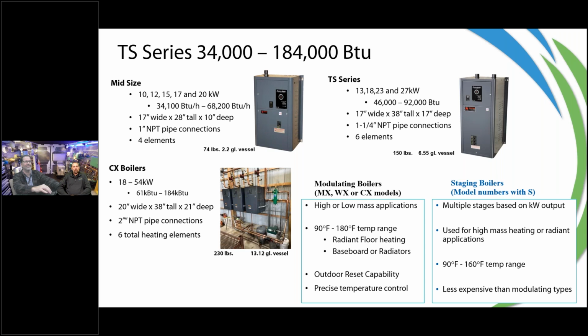It's BTUs. If I can give you a piece of equipment and a terminal unit, whether it be radiant heat, that's where the conversation always turns, because radiant, what temperature are we running that for? 100 degrees, 115 degrees, maybe some radiant applications a little higher, 120. We're heating houses all day long with radiant, whether with air to water or hydronic air handlers at 120 degrees. It's not the temperature, it's the BTUs.